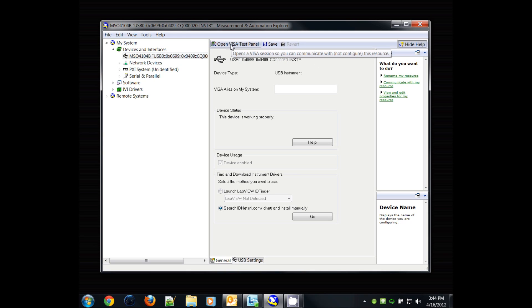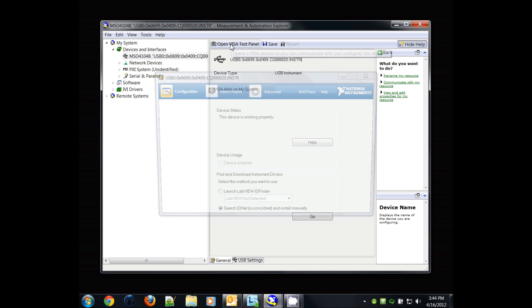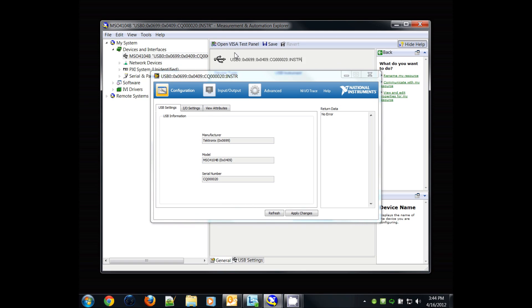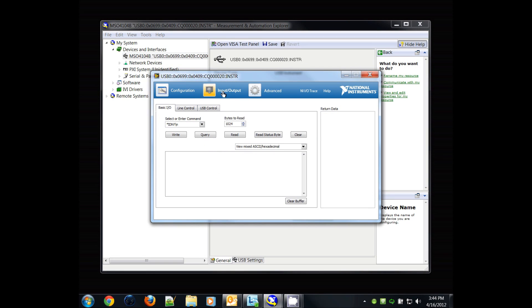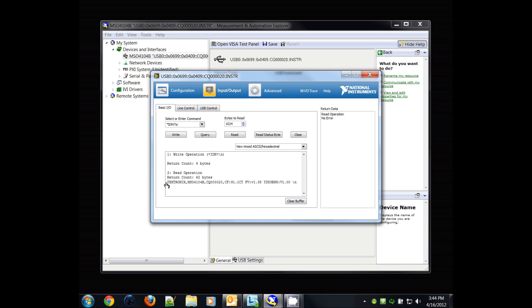I'm going to open up the tools for this, go to input-output, and I'm going to do a *IDN?, which is an identification command. I'm going to press the query button and you'll see this instrument pop up in the list.